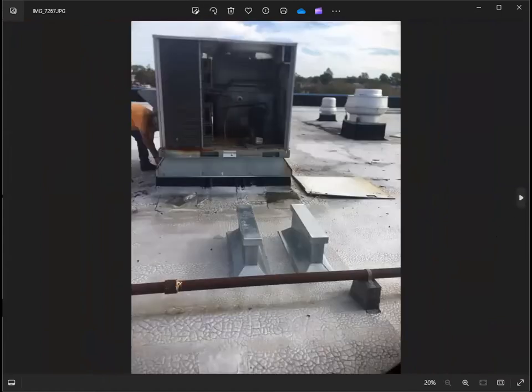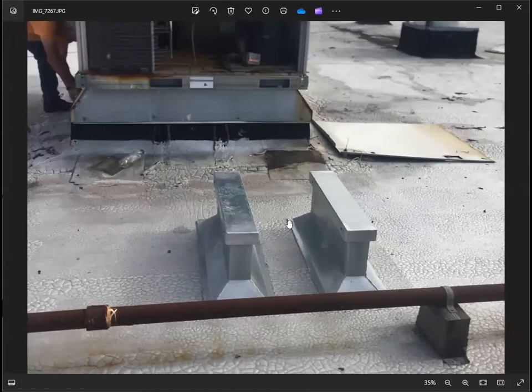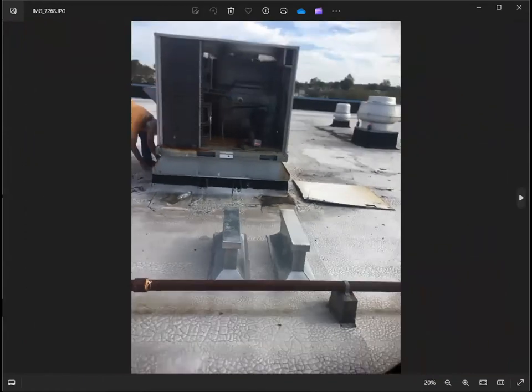And some installations. The rooftop unit wasn't installed yet. So this is the mounting base for the rooftop unit, and this is the supports for your refrigerant piping vertically. This is the ladder going to the roof, and they have supported the piping through the wall.